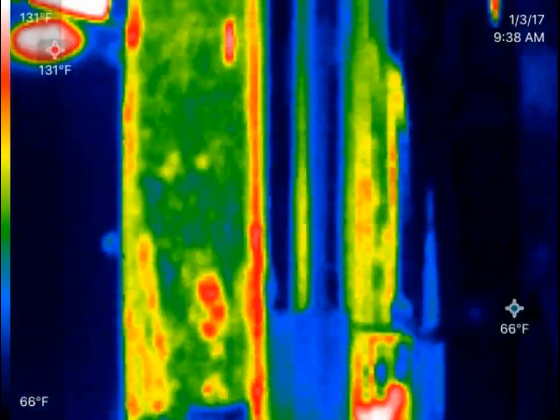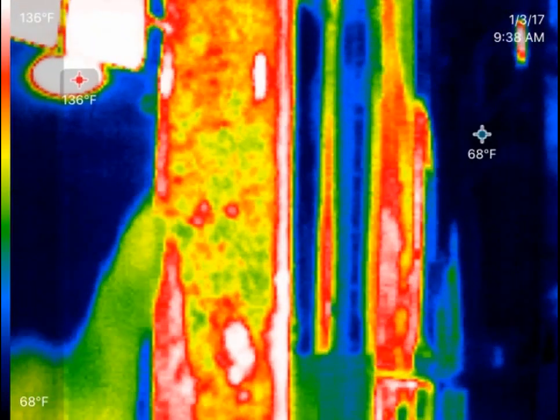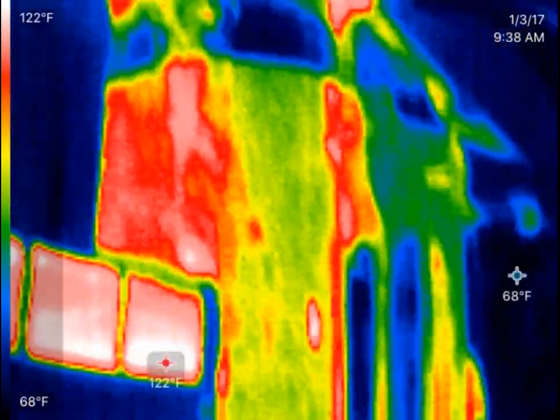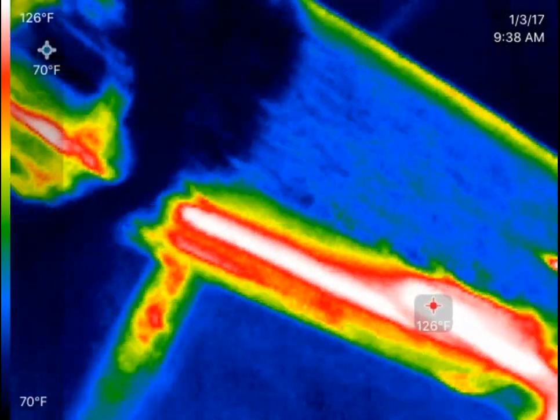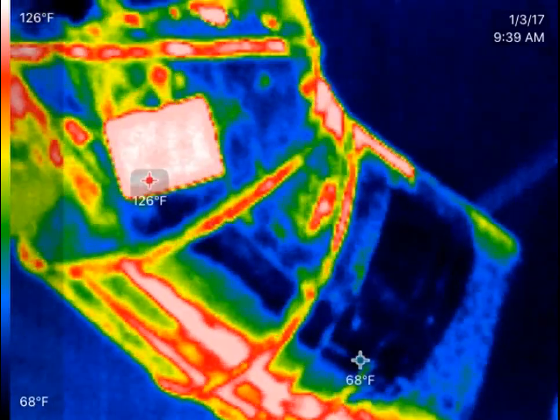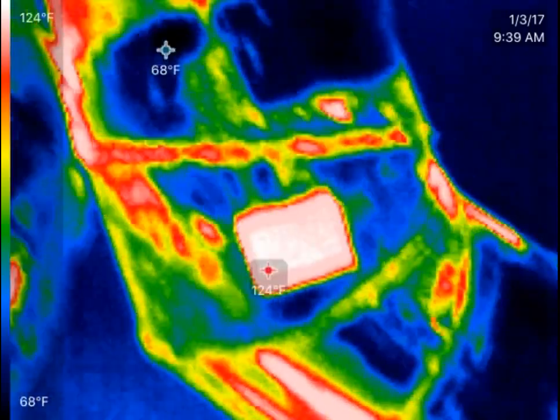And then as you get into the ductwork, you can see this is the ductwork here — right there. We're showing it kind of green, which is a good color. A few warmer spots there. And some stuff like this here is actually a label, which is no hotter than the rest — it just reflects back differently.